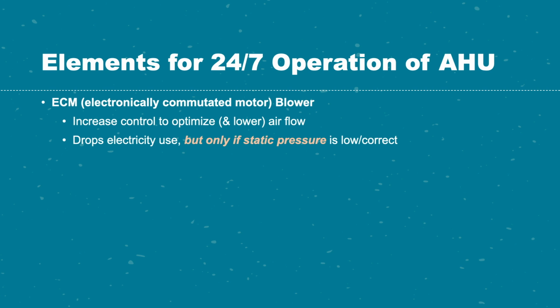So with an ECM, electronically commutated motor, you've got more control over airflow. So you can set it to a lower setting and you can also drop the electricity use. However, static pressure has to be correct. The worst systems we saw were systems that had an ECM blower, but a very restricted duct system. And in that case, the energy use was far worse than the old-fashioned inefficient blowers, interestingly.